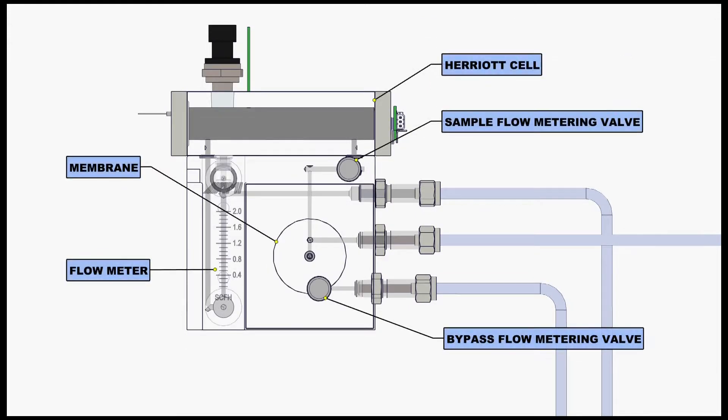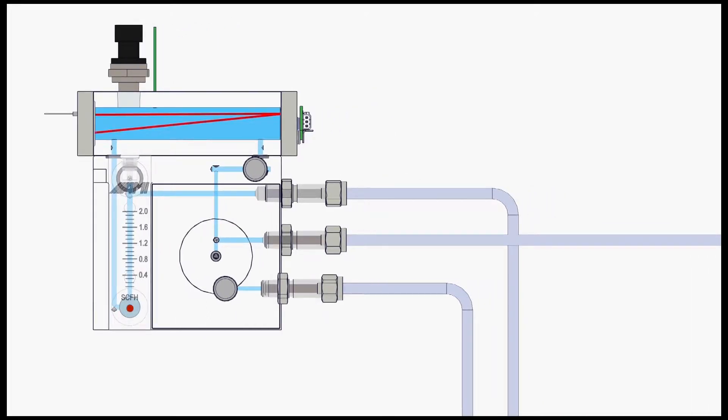First, at the center of its design is AMI's next generation of proven cell block technology: the liquid eliminator cell block. All critical sample handling components, including the flow meter, metering valves, liquid separation membrane, and Herriott Cell, are all integrated into a series of solid compact blocks with machined intersecting passages in place of long lines of tubing and off-the-shelf components. This innovative design virtually eliminates all potential leak paths and significantly minimizes the volume and distance that sample gas must travel prior to entering the laser chamber.